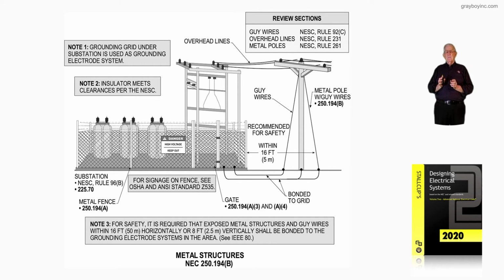Now, review the metal pole with the cross arms to the right of the substation. It says it's a metal pole with guy wires in accordance with 250.194B. If any of that equipment pertaining to that metal pole falls within 16 foot of that fence as outlined in Note 3, it has to be bonded into the grid system so that the fence, the grid system, and all the equipment in the substation between these areas are considered as equal potential as possibly could be designed and installed. So figure 16-141 deals with metal structures in accordance with NEC 250.194B, as in boy.